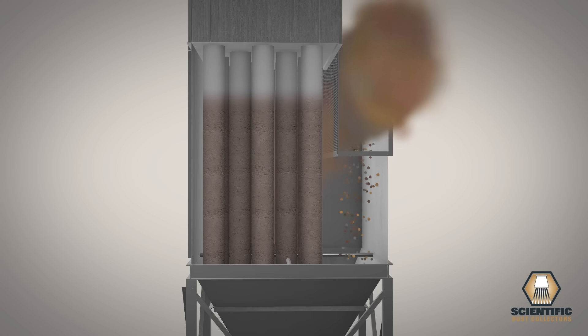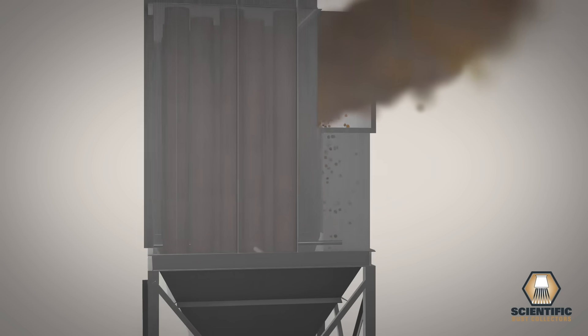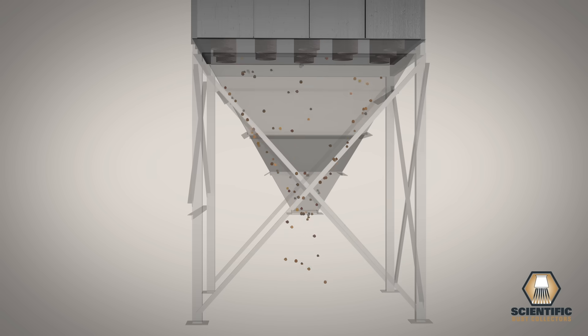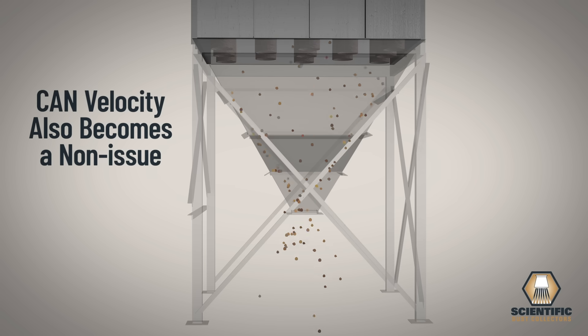Coupled with a slowed inlet velocity at less than 3,000 feet per minute, larger particles are allowed to fall out prior to reaching the filters, which greatly extends the filter life.